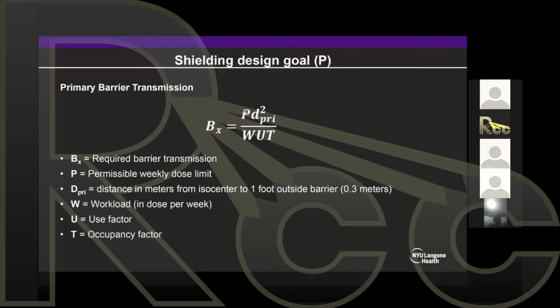So here P is your shielding design goal. And as I said, we basically have two numbers: 0.1 for controlled and 0.02 millisievert per week for uncontrolled. And the rest of the parameters, very important, are the workload, the use factor, and the occupancy factor, which I'm going to talk about in the next slides. This is just the distance in meters from the isocenter. It will normally be 1 meter to 1 foot outside of the barrier, where you're going to measure during your survey. And this will calculate your barrier transmission. So when you are designing shielding, you know how much shielding you need to add.